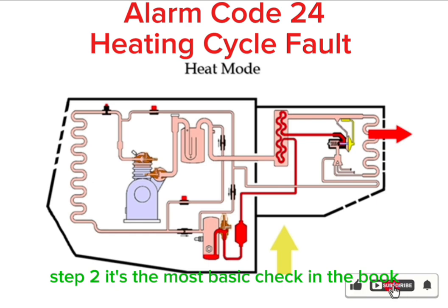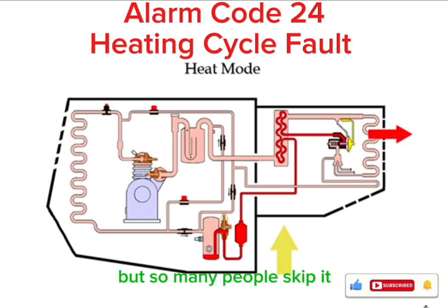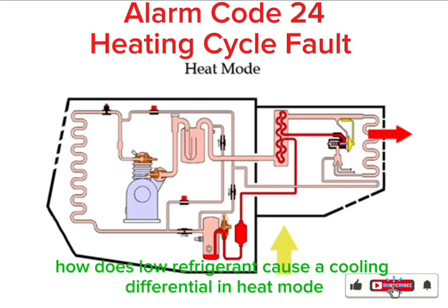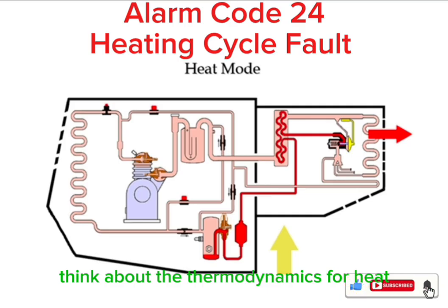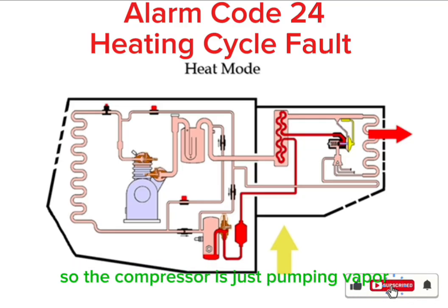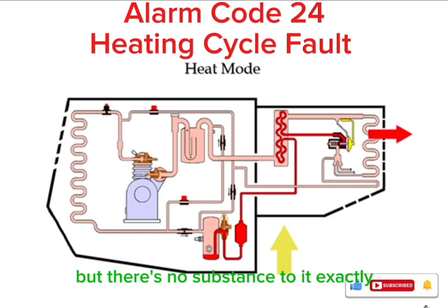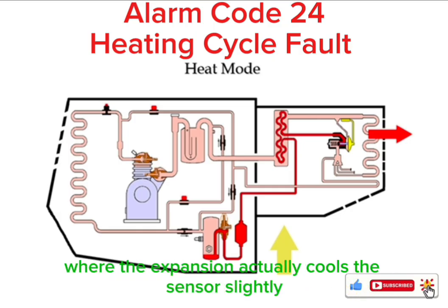Yeah. Step 2. It's the most basic check in the book, but so many people skip it. Check the refrigerant level. That seems almost too simple. How does low refrigerant cause a cooling differential in heat mode? Think about the thermodynamics. For heat, you need hot gas. You need mass flow. If you're low on charge, you don't have enough gas to build the pressure you need to generate heat. So the compressor's just pumping vapor, but there's no substance to it. Exactly. You might get a little bit of movement, maybe enough to drop the pressure, but not enough to create heat. It can create this weird state where the expansion actually cools the sensor slightly.